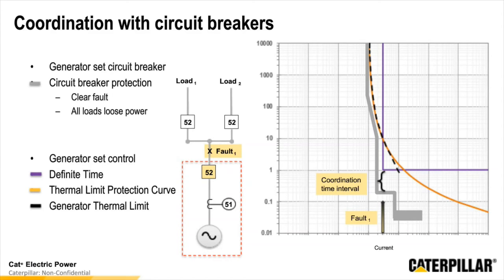So now we're starting to look at this coordination function and how we coordinate these different breakers within a system. As you can see, we've now brought that relay protective and the generator breaker all together on the same graph. And now what we're looking at is, as we go up into the long time settings, we're able to follow the curve as much as possible. This allows us to give as much current as we need from the generator, and as much as we're capable of providing, without tripping the generator breaker.